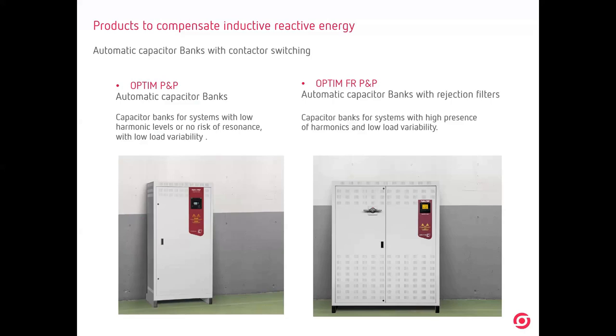What does it mean? If we go to the industry and we are measuring with a power analyzer, portable or fixed, and we have harmonics, okay? These harmonics can damage the capacitors inside the capacitor bank, because the capacitor absorbs all the harmonics that you can have inside the installation. If the capacitors absorb the harmonics, you are overheating the capacitor, and it will die in a period of time, okay? So this is why we are offering two things: a capacitor bank with or without reactor filter.